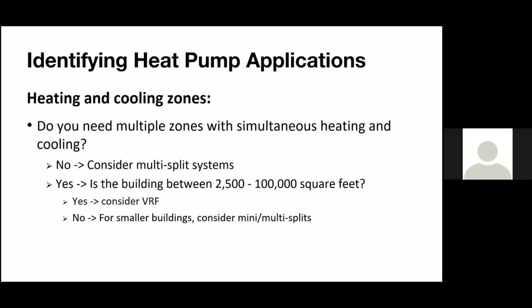And then also, if you're looking at a smaller office fit out, right, you maybe only need 5 tons of cooling capacity. Maybe just an open office space with like 1 or 2 offices. That might be a good opportunity to just provide mini splits. Don't get a huge VRF system that's 3-phase. Maybe just use a single phase condenser there and supply the load that way.